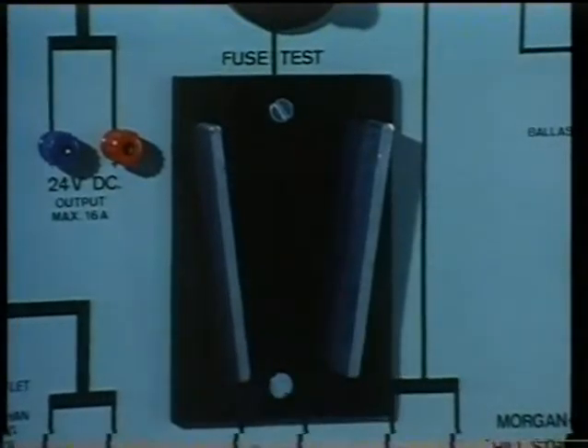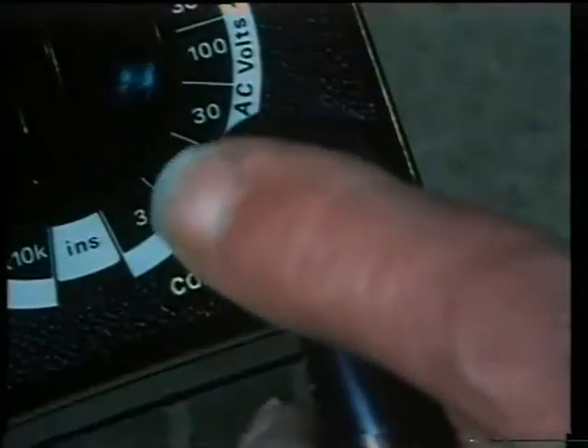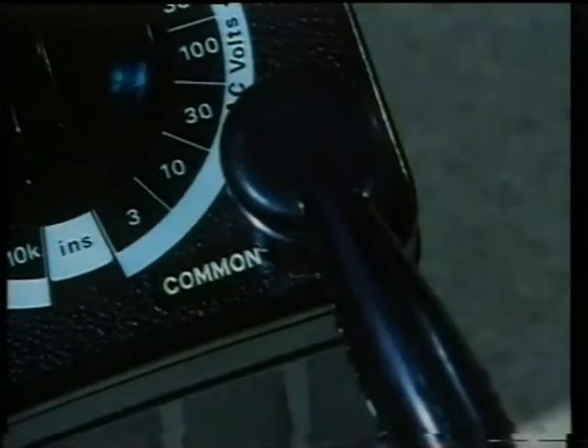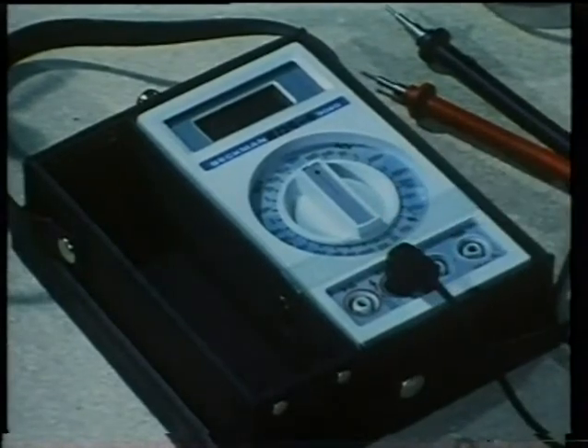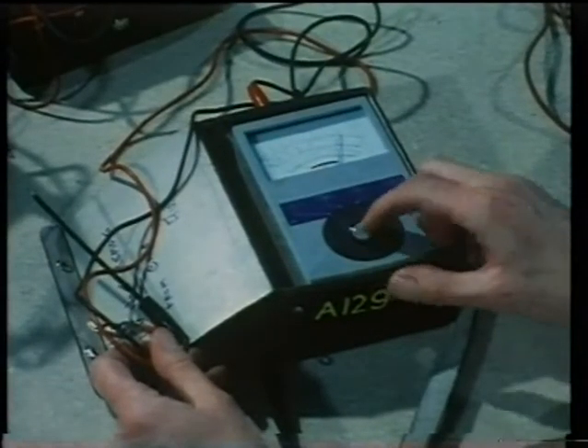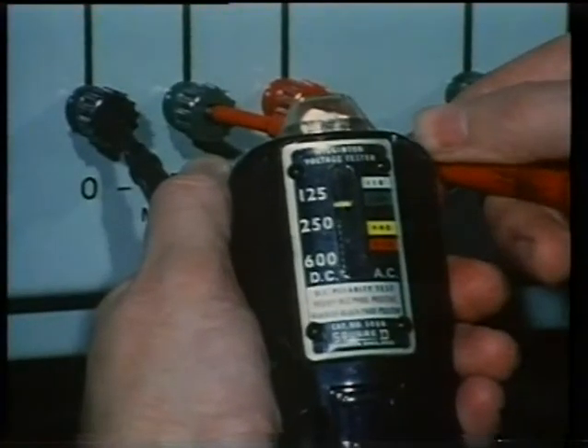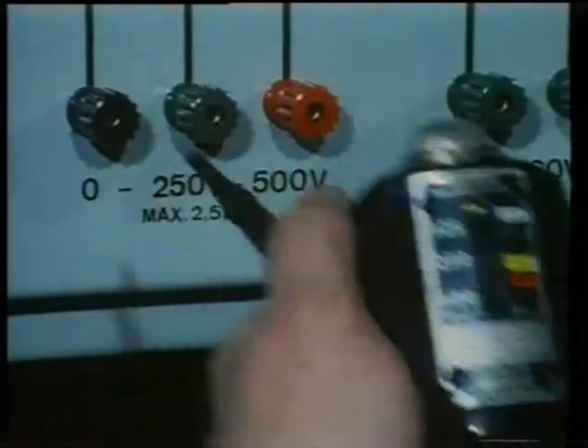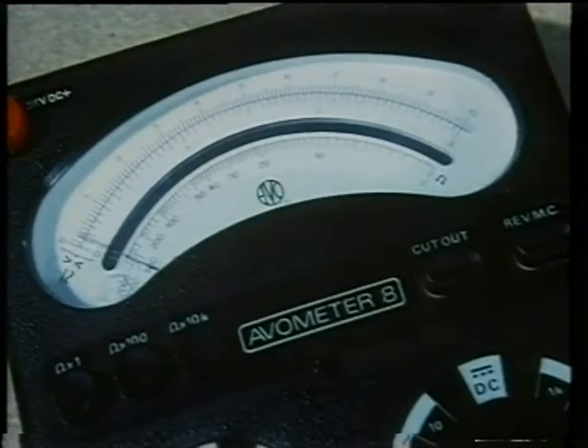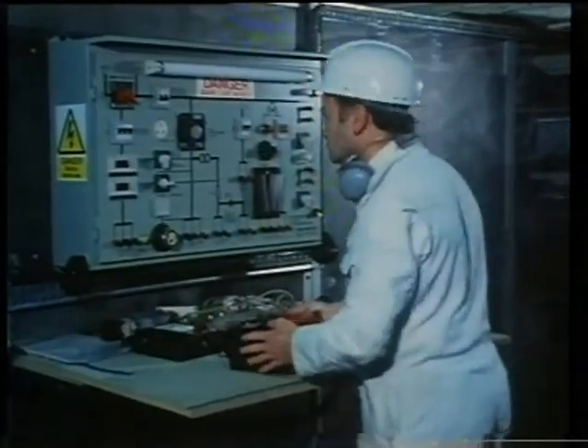The most frequently used test meters are multimeters, insulation resistance testers, and line testers. A multimeter can be analog or digital type, and we'll describe their setup procedure here. First, an analog meter. For easy reference, the setup procedures are listed on the back of the meter or in the user manual provided by the manufacturer.